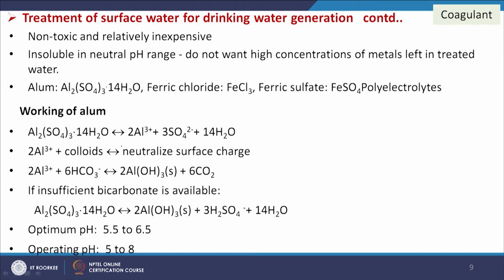Common coagulants include aluminum sulfate Al₂(SO₄)₃·14H₂O (alum), ferric chloride FeCl₃, ferric sulfate Fe₂(SO₄)₃, and polyelectrolytes. These materials are normally non-toxic and relatively inexpensive — it is important they are non-toxic since toxicity would be dangerous for health. They are insoluble in the neutral pH range and do not leave high concentrations of metals in the treated water.